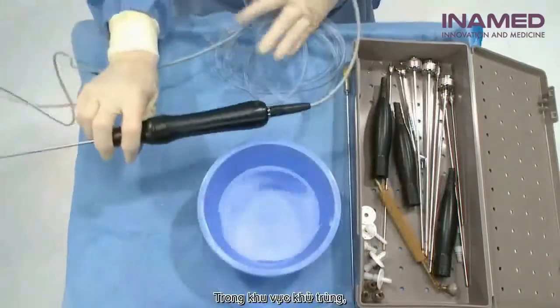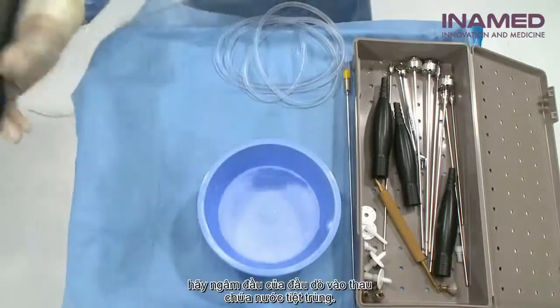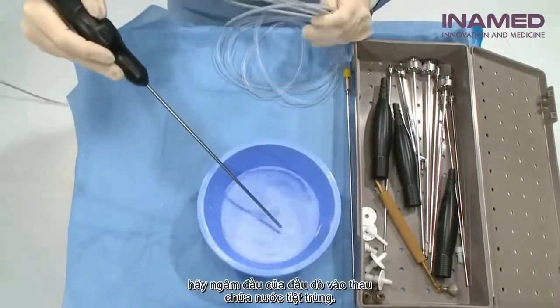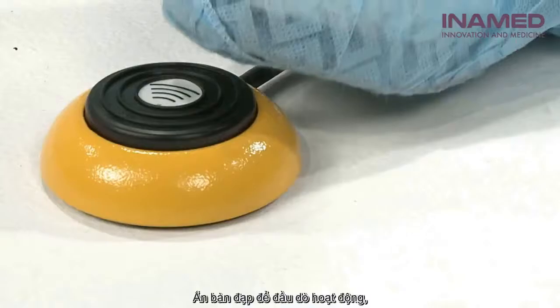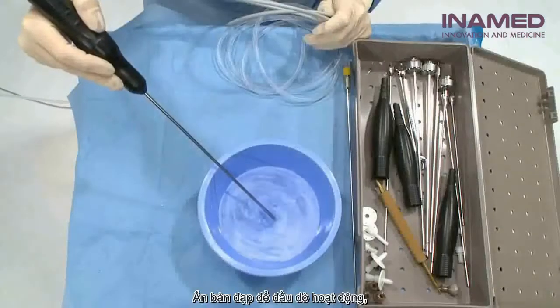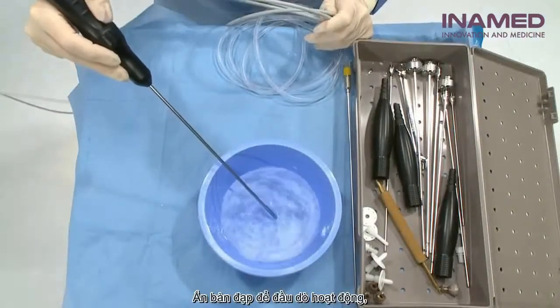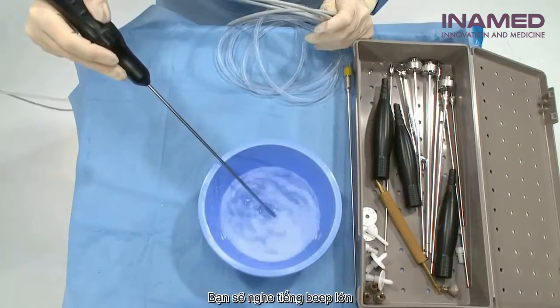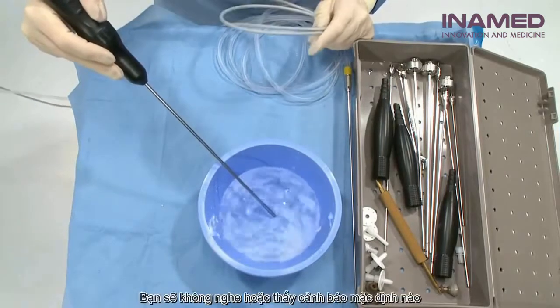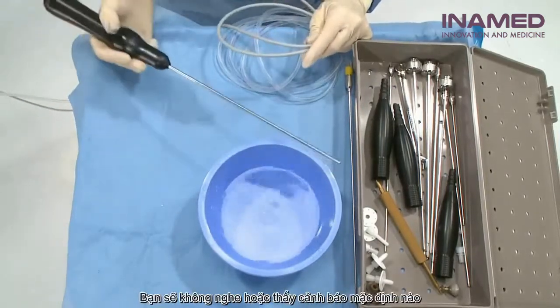In the sterile field, completely immerse the tip of the probe into a cup of sterile water. Depress the Vaser foot switch. If the handpiece is working properly, you should hear a high-pitched sound and see bubbling in the water. You should not see or hear any fault warnings.